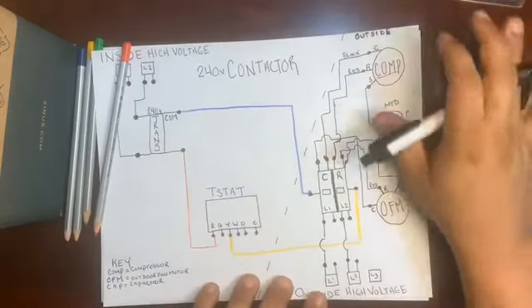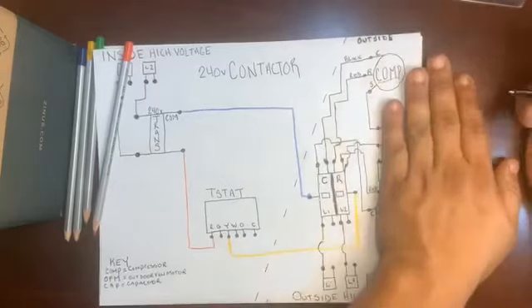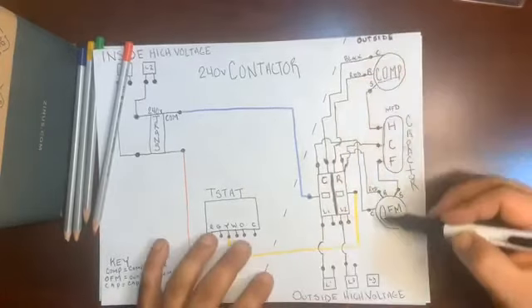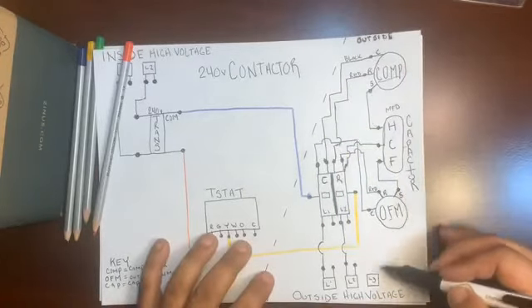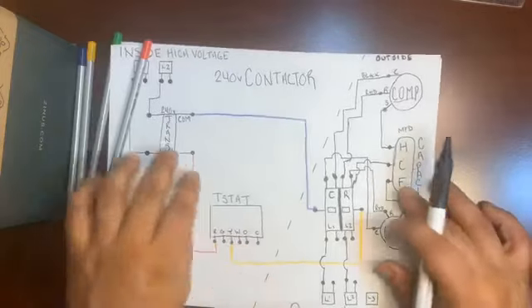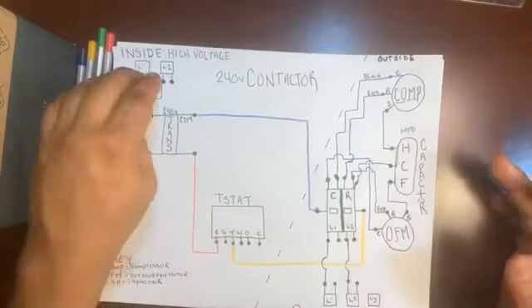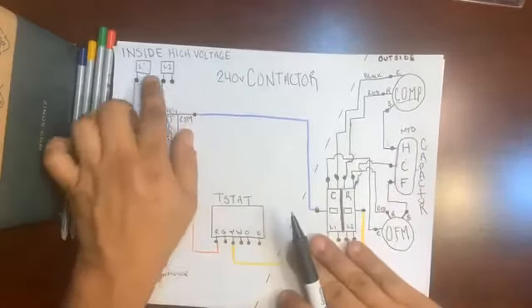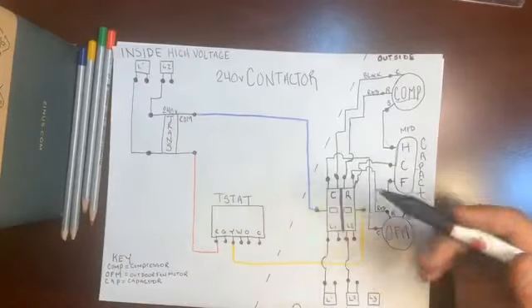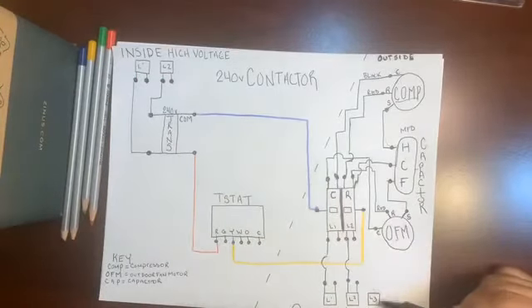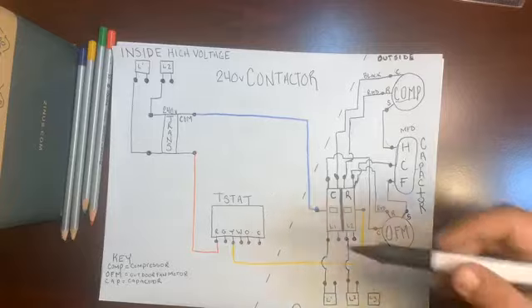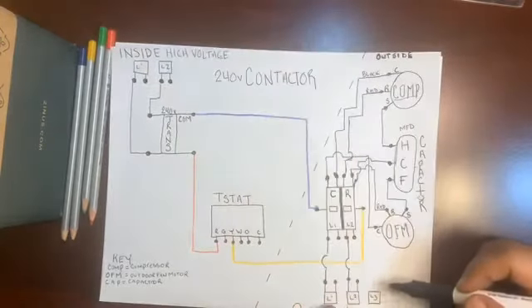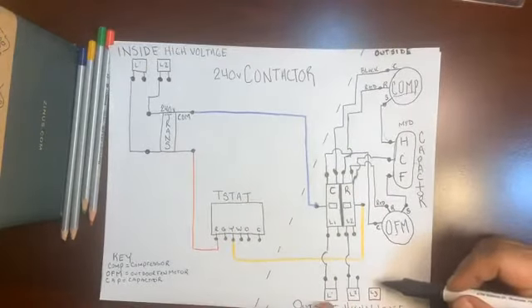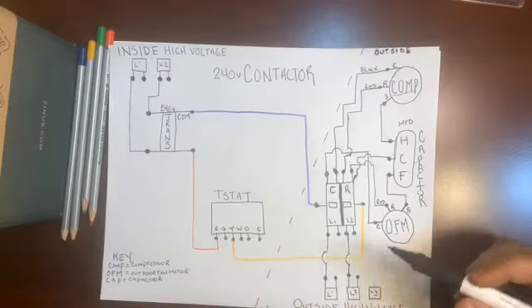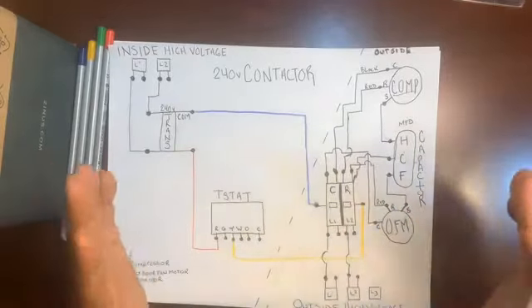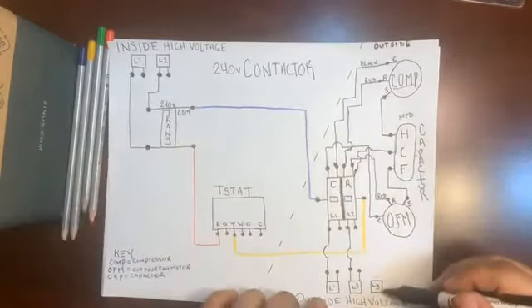Because if we didn't have this capacitor, this start leg would have to go to L3, and this start leg would have to come down to L3. When we're doing residential, you're only going to experience 240 volts. When you get up on rooftops, now you're doing 3 legs of energy, 3-phase power. This is 3-phase power, this is 2-phase power. When you work on L3, when you work on a machine that has 3 phases of power, every time you take off the panels, you have to say a prayer, because this can literally kill you.